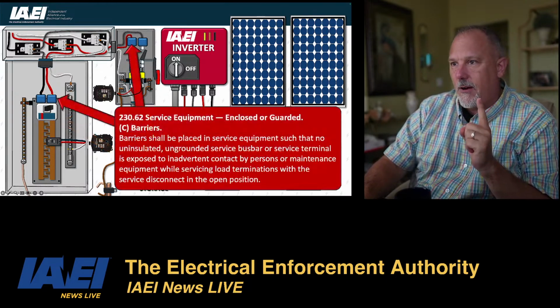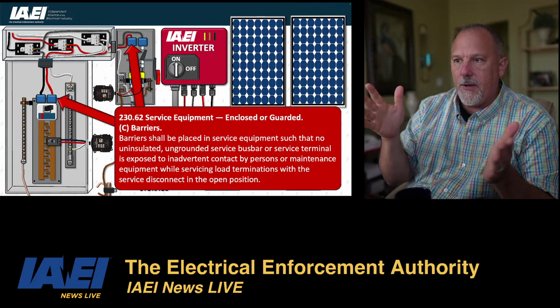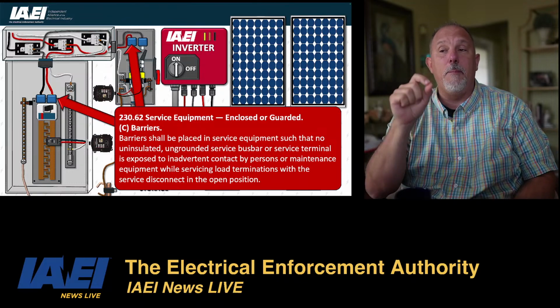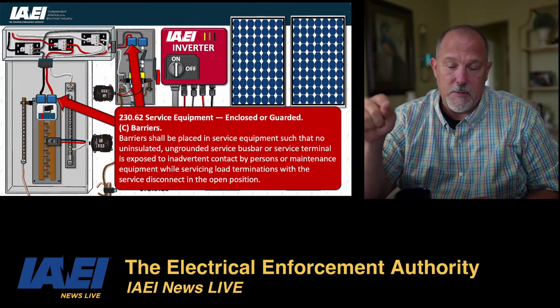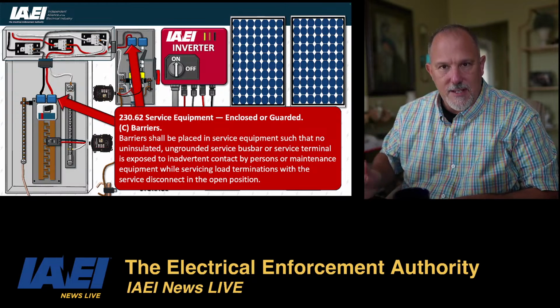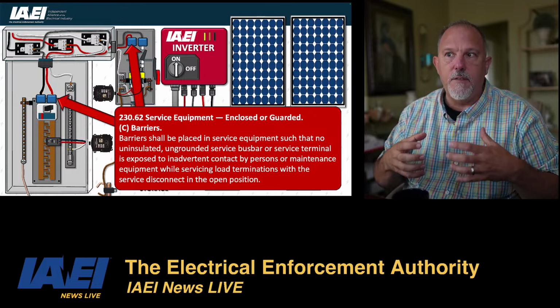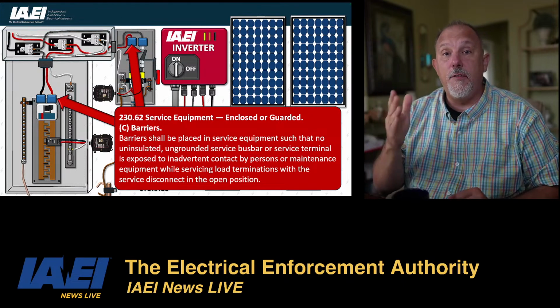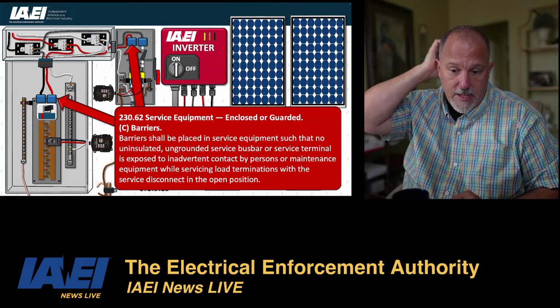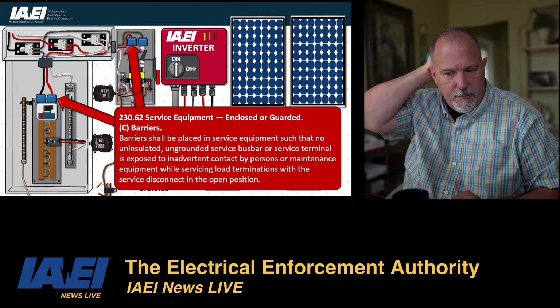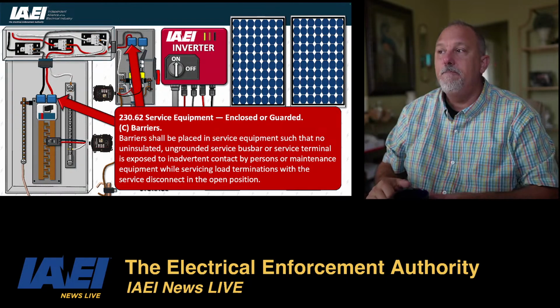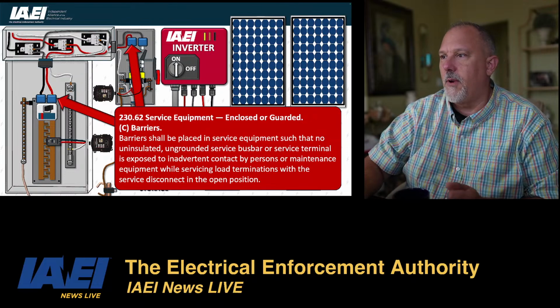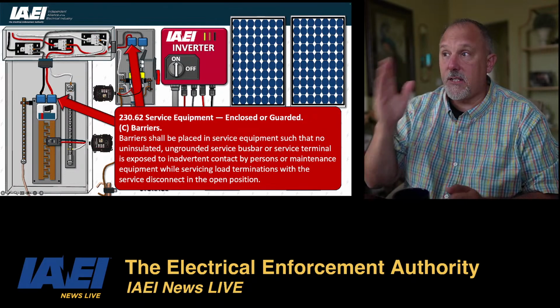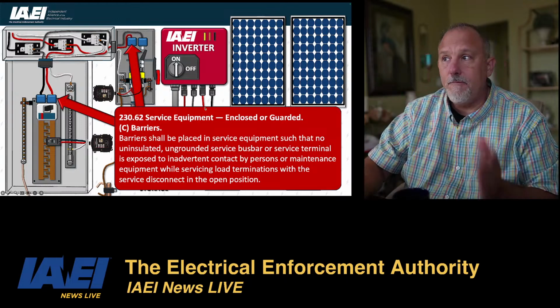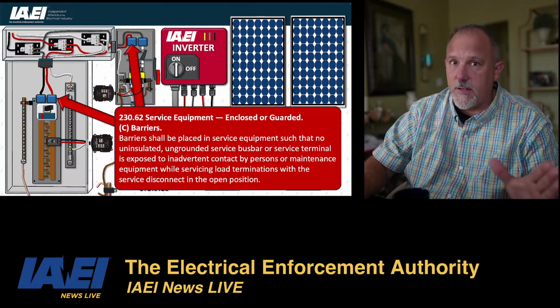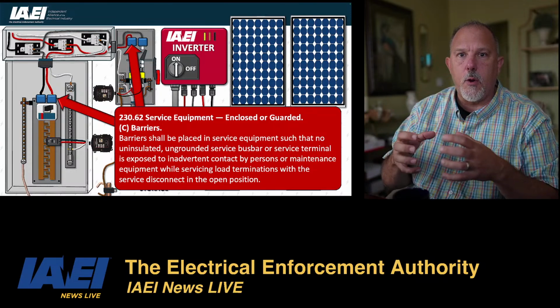So let's continue on. There's our 230.62 barriers. Those are required. And that's the real important part about calling these service disconnecting means. The moment you call something a service disconnect, you bring in the requirements of services, and the barriers are one of those important items. The CT meter is owned by the utility. Very good. Thank you for bringing that in. Yes, the moment you call something a service disconnecting means or service equipment, you bring in the requirements of Article 230.